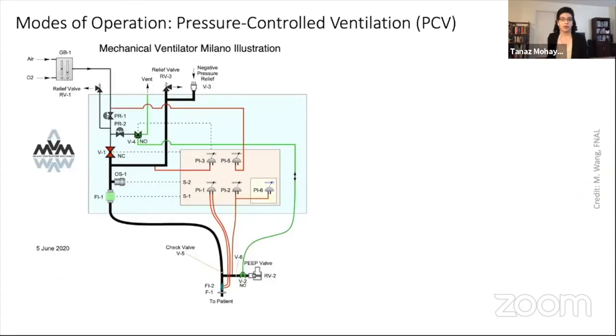Let's go over the pressure controlled ventilation, or PCV mode, first. You already remember this diagram. Here's how the MVM valves operate in this PCV mode: the expiration valve at the bottom, shown in red, closes, while the other valve that controls the incoming airflow at the top, shown in green, opens to allow medical air mixed with a fraction of oxygen to flow to the patient.